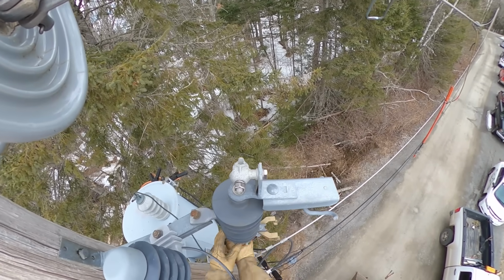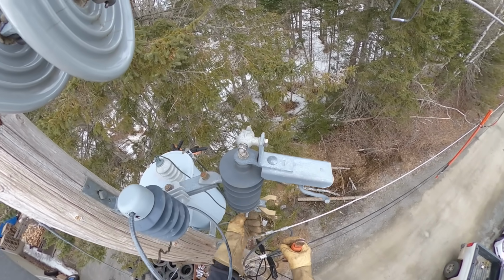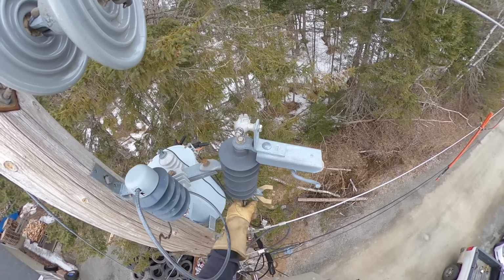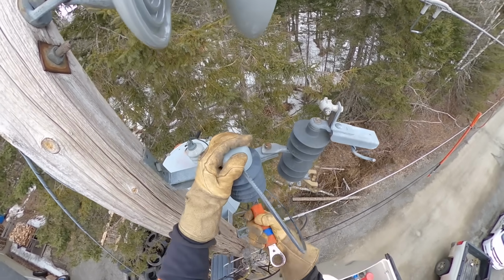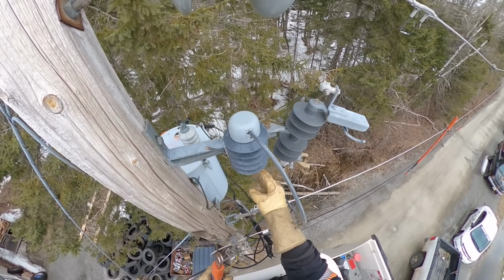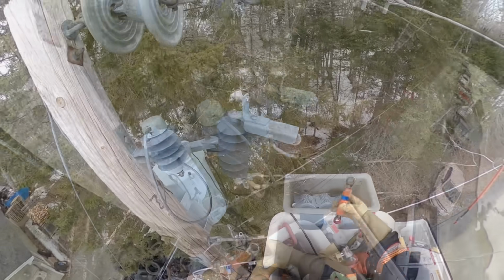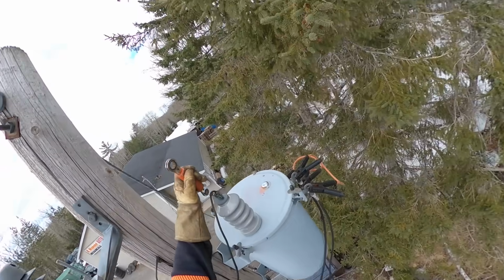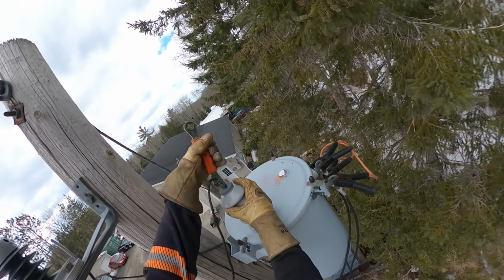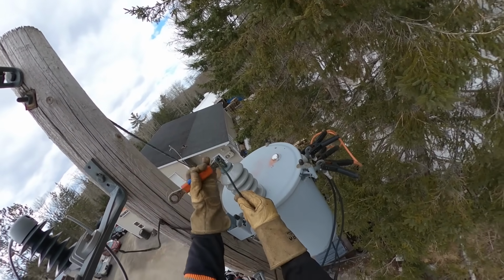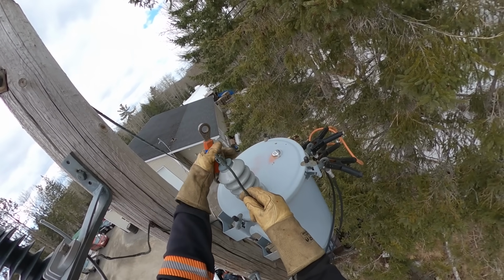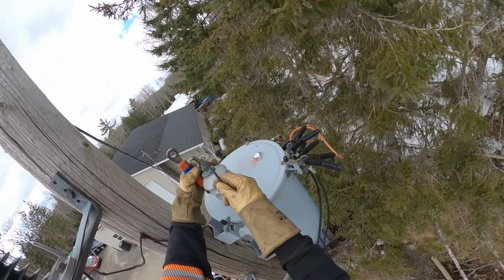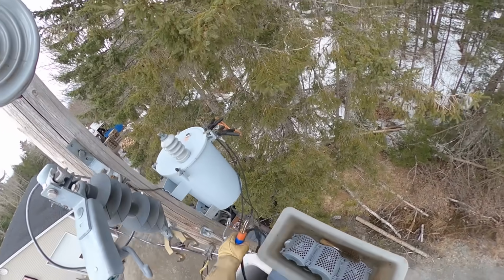So taking the primary lead out of the transformer, that's a bare copper wire. Years and years ago, that's all we ran from the transformer to the cutout, just bare copper wires. Now where we do have so many squirrel and bird incidents, we have 2 options. We have what we call bird wire, which is copper with a really thick insulation. It's kind of hard to peel. That's what this is in my hand right now.